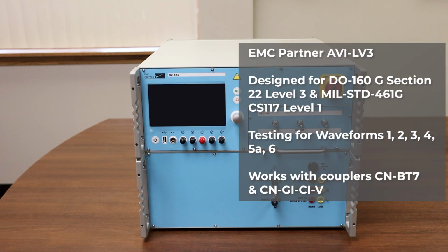The EMC partner AVI-LV3 is designed for DO160G Section 22 Level 3, as well as Mil Standard 461 CS117 Level 1 for internal equipment. The AVI-LV3 is the newest model with similar capabilities as the AVI 3000, which we did a video on previously. This test system provides capabilities for waveforms 1, 2, 3, 4, 5A, and 6.